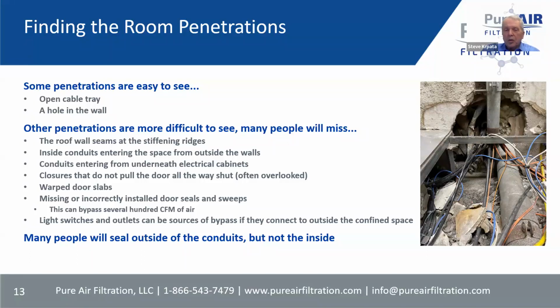We know enough to look under those floors, pick up those tiles, and search through all that stuff. The same thing with ceiling tiles. Ceiling tiles hide a lot of ills above them, and you have to pop those up and look. Another thing commonly missed is the roof wall seams for a lot of the rooms. That's typically a bypass, especially on the ends of the roof that have the stiffening ridges. The indentations created by the stiffening ridges are a bypass to the outside and need to be sealed if you want a good room sealing job.